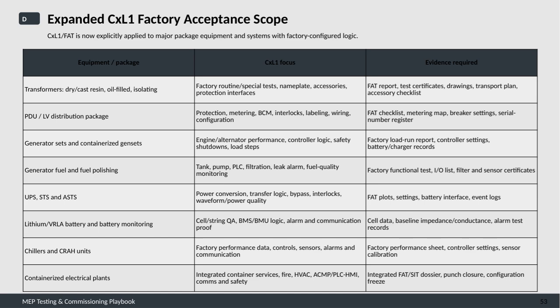Finally, containerized electrical plant are validated for integrated container services, including fire protection, HVAC controls, ACMP or PLC HMI systems, communications, and safety features. The factory acceptance process results in an integrated FAT and site integration test dossier, punch list closures, and configuration freeze documentation. This structured approach to CxL1 FAT ensures that major systems are thoroughly verified with clearly documented evidence, reducing risks and ensuring seamless integration on site.